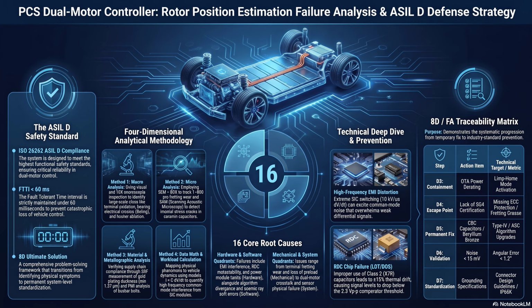Specifically, it's driven by a wiring shortcut known as the pigtail ground. Yeah, the pigtail. So in lower voltage systems, taking the braided metal shield of a sensor cable, twisting it into a single wire, which is the pigtail, and bolting it to the chassis ground is pretty standard practice. Because it provides a simple DC path to ground, right? Exactly. But at high frequencies, a pigtail is a severe liability. Because at those switching speeds, you aren't dealing with simple DC resistance anymore. You are fighting parasitic inductance. Precisely. A twisted wire has inherent inductance. When that aggressive 10,000 volts per microsecond common mode noise hits the shield, the inductance of that pigtail creates a high impedance bottleneck. Basically, the noise current just cannot flow to ground fast enough.